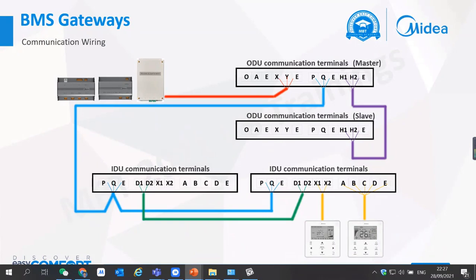You will see that a lot of controllers now, because the indoor unit does not have XYE, connect through it instead. The central controller connects to the XYE, the BMS gateway connects to the XYE, CCM15 connects to the XYE, but the outdoor unit only has one XYE port. So if I want to connect CCM15 as well as BMS, how will I do it? We have a solution for that also, which we will show you in the next slides. So for now, outdoor unit side will connect these 3, and indoor unit side will connect the KNX gateway.